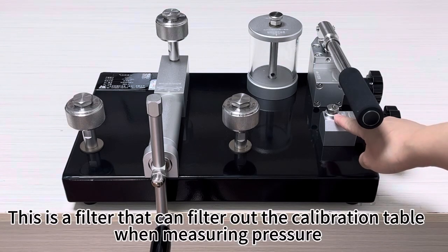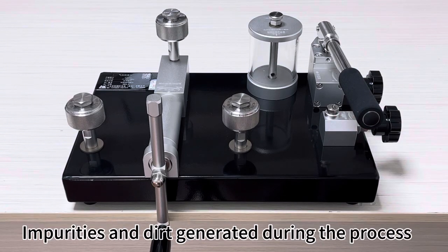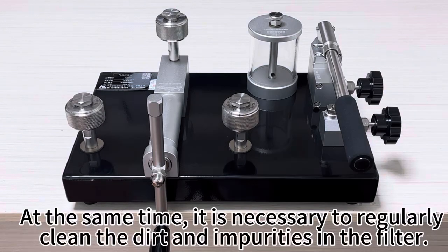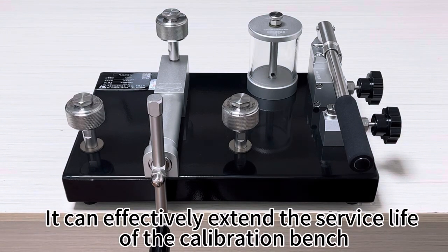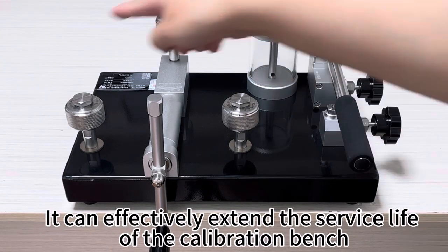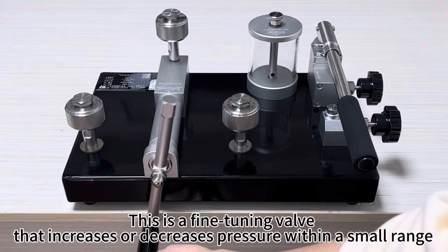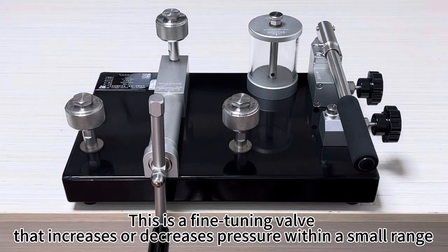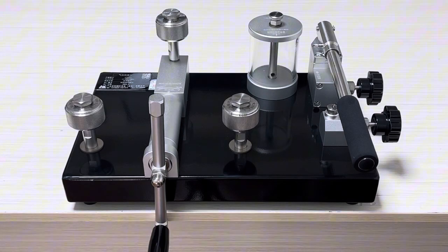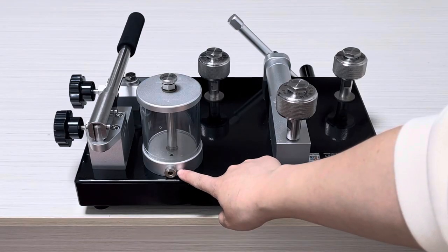This is a filter that can filter out impurities and dirt generated during the calibration process when measuring pressure. At the same time, it is necessary to regularly clean the dirt and impurities in the filter. It can effectively extend the service life of the calibration bench. This is a fine-tuning valve that increases or decreases pressure within a small range. This is the drain port.